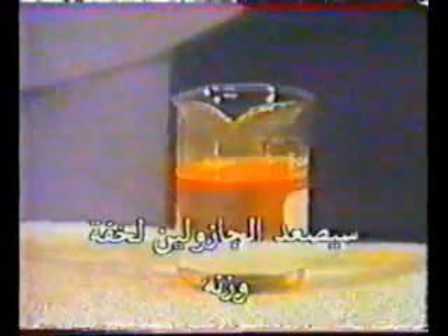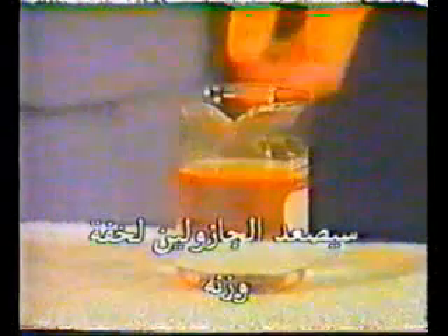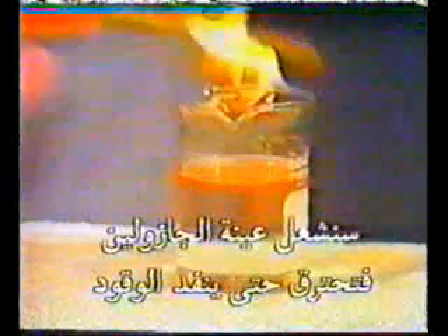Suppose we put water and gasoline into the same container. The gasoline will rise to the top because of its lower weight. We can ignite this sample of gasoline and it'll burn freely until the supply of fuel is exhausted. Since most liquid fuels are lighter than water, care must be exercised when applying water to these types of fires. If hose streams are improperly splashed into the fuel, the additional water may only serve to spread the fire.